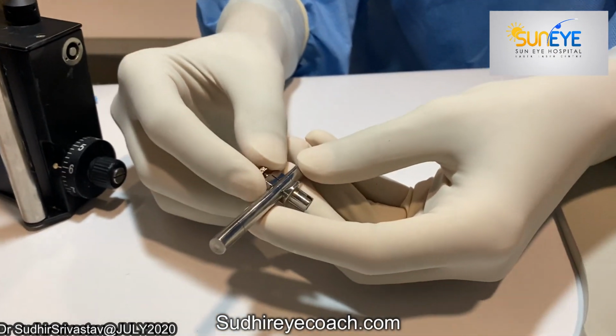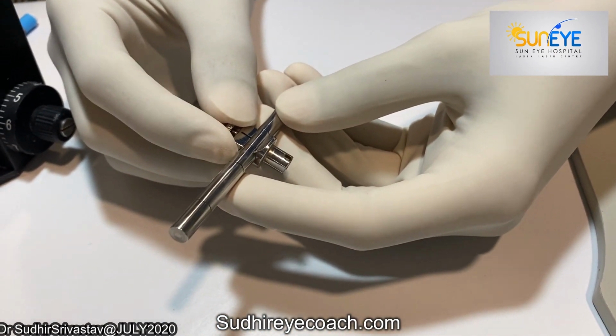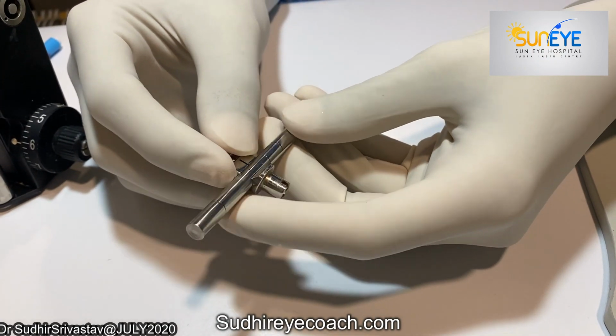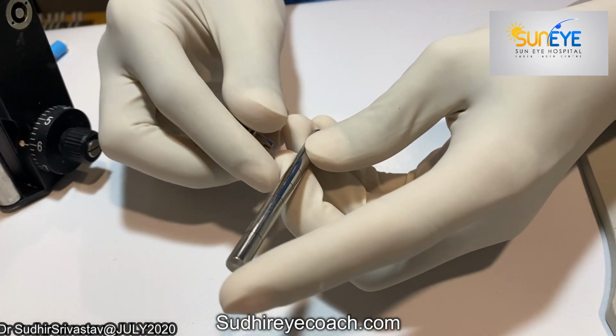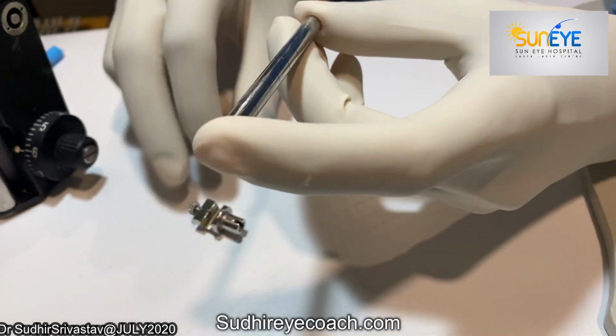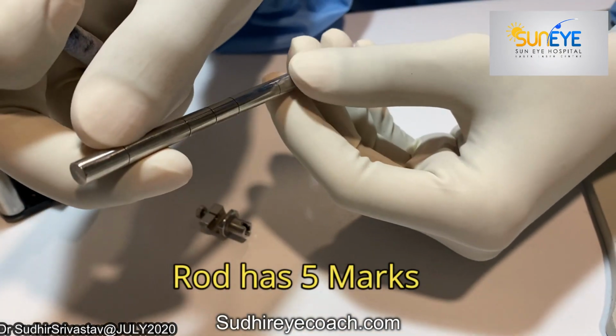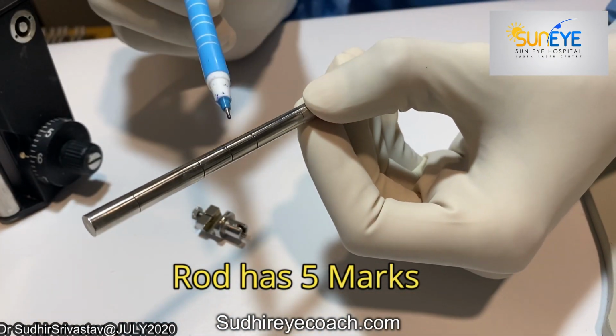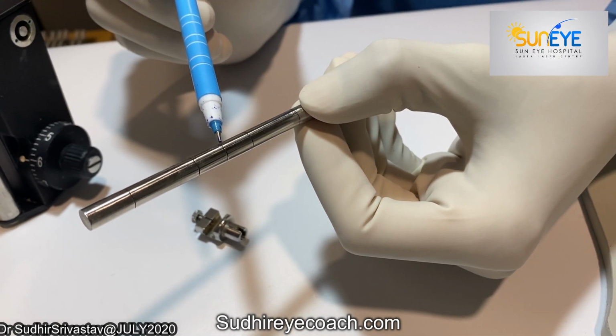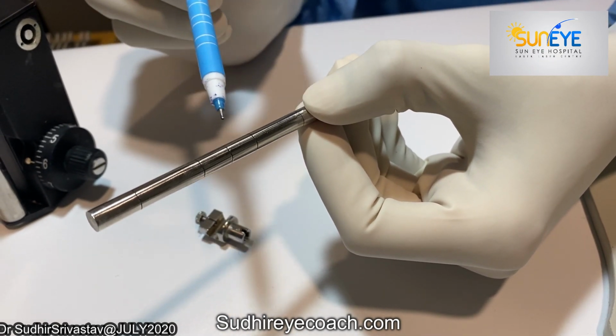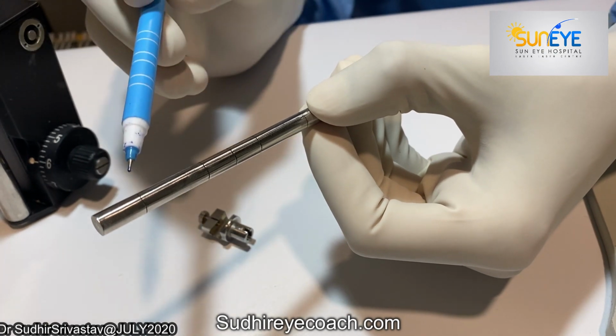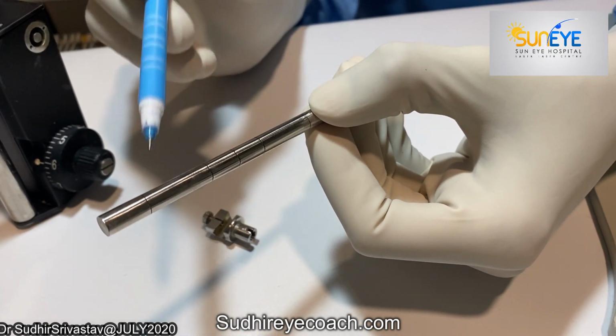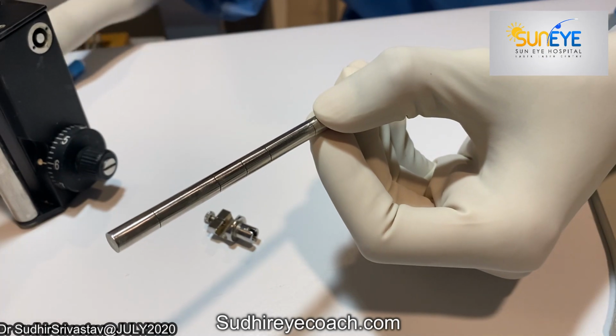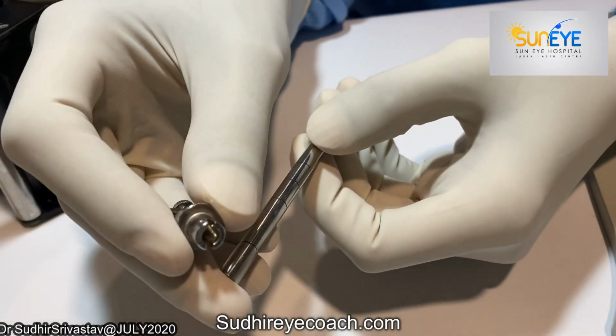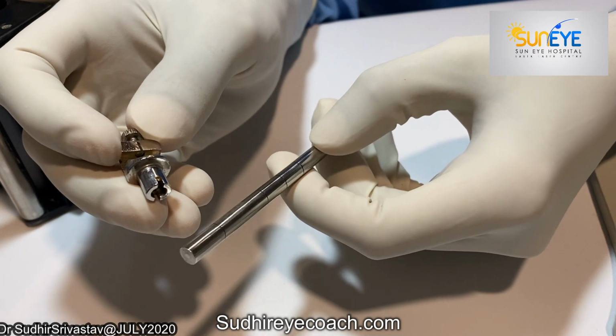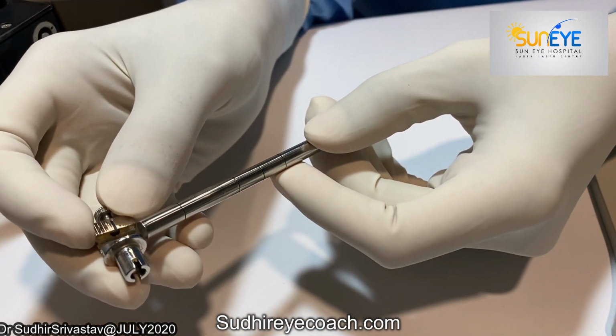Now, this is the device or gadget to check the calibration of the applanation tonometer. It has two parts. This part is the steel rod. As you can see, it has 5 markings on it. The central marking corresponds to 0 millimeters of mercury. The second marking on either side corresponds to 20 millimeters of mercury, and the third reading on both sides corresponds to 60 millimeters of mercury. This part is called a weight balance or weight device, which has to be mounted on the steel rod like this.